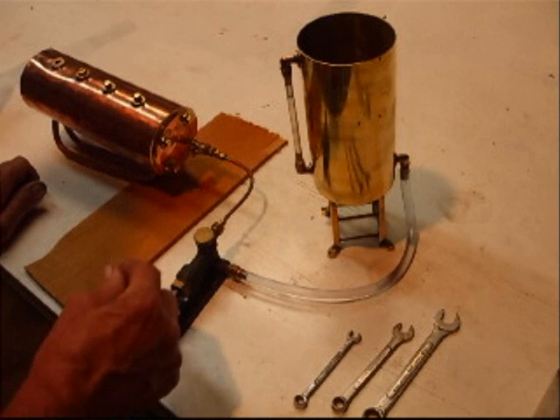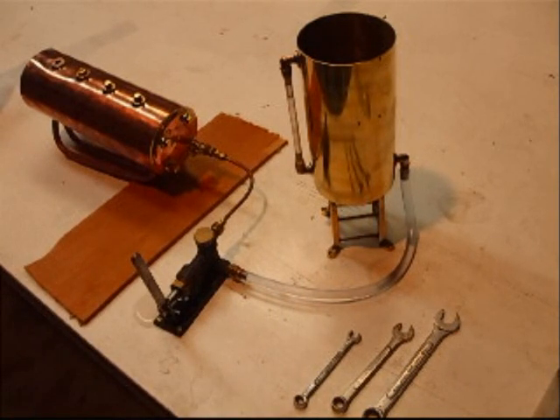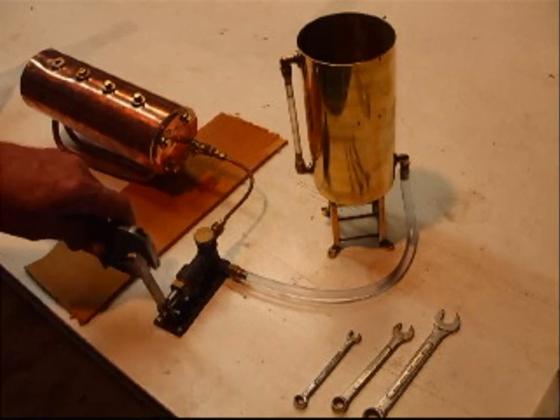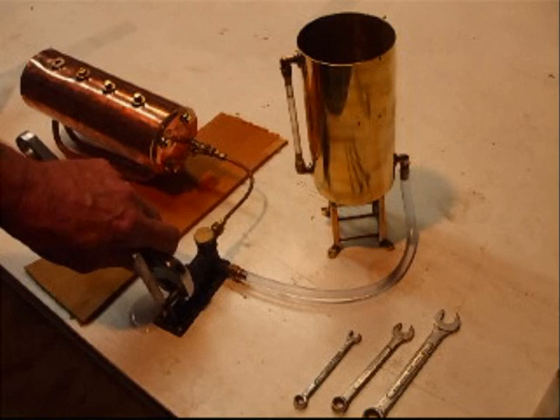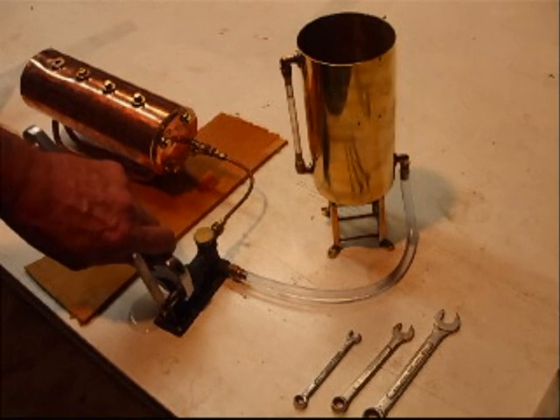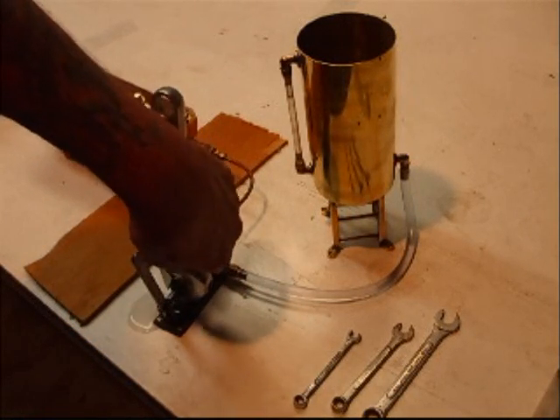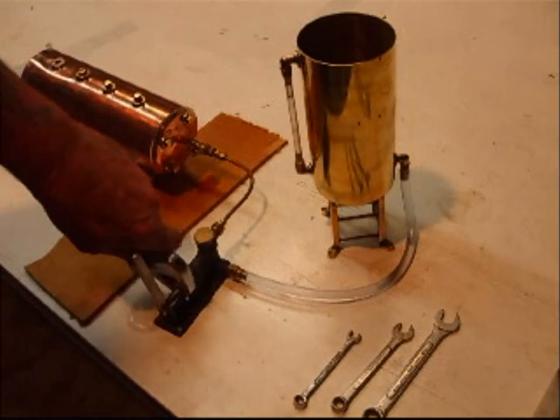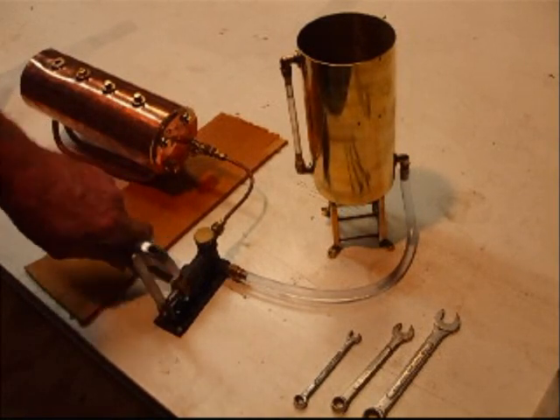Yeah, we're leaking. I'll just tighten the gland. If it's leaking from the gland, it'll probably be sucking air too and not pumping properly. You can't afford to have any leaks with these.